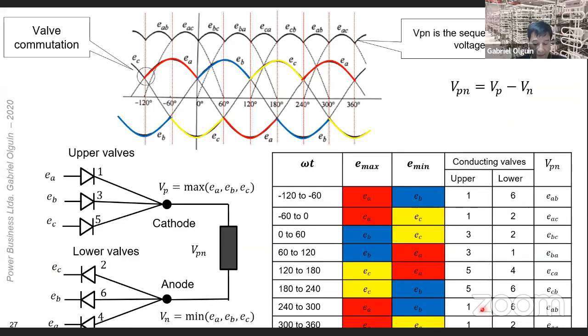This slide explains the commutation or conduction period of each thyristor valve in more detail. I have opened the converter bridge for a better understanding. Again, upper valves 1, 3, and 5 share the cathode, and hence the maximum phase voltage will appear at the converter positive terminal. The maximum voltage will appear here. On the other hand, the lower valves 2, 6, and 4 share their anode, and hence the minimum phase voltage will appear at the converter negative terminal.